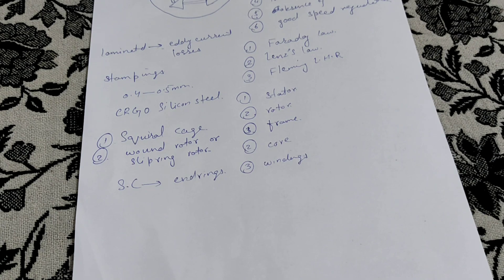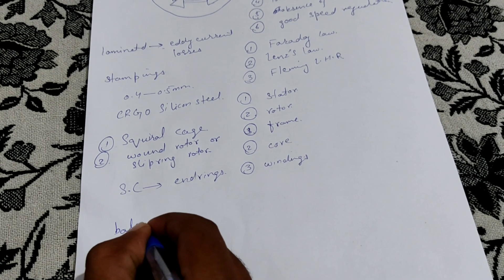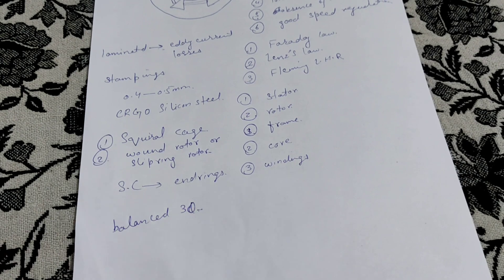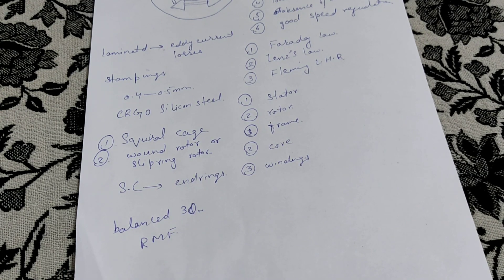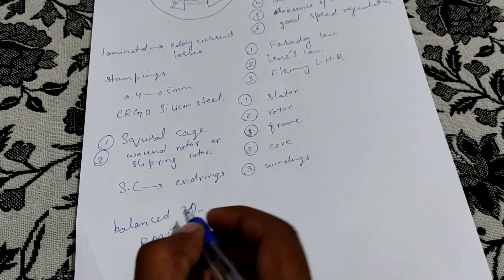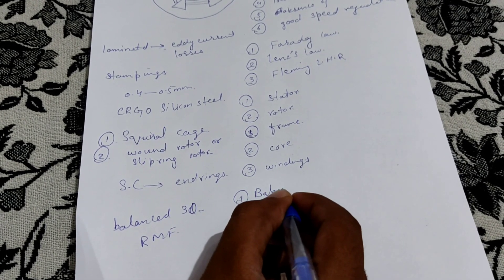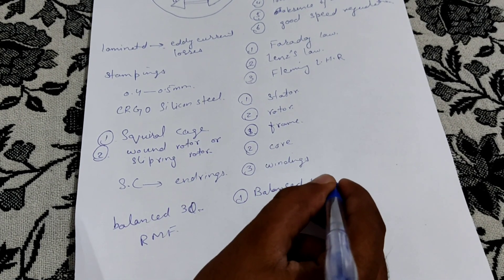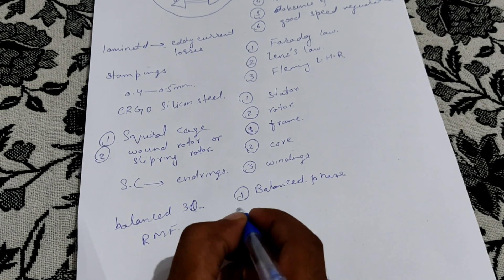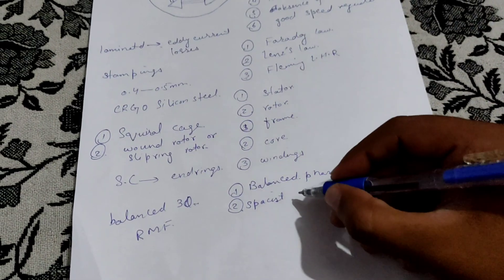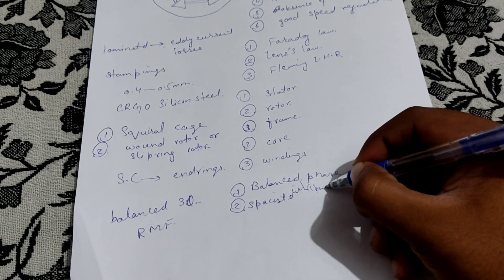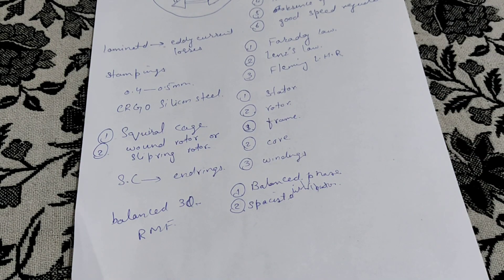Now coming to the working principle of the three-phase induction motor: when a balanced three-phase supply is provided to the three-phase stator winding, a rotating magnetic field (RMF) is produced. The concept behind the RMF requires two conditions: number one is a balanced three-phase supply, and number two is a distributed winding.